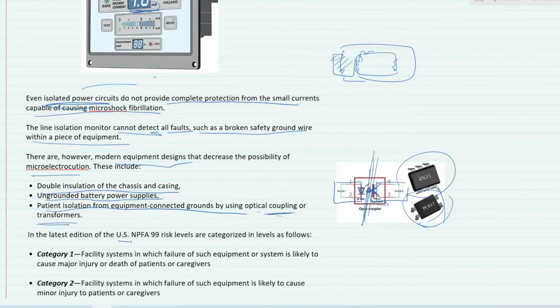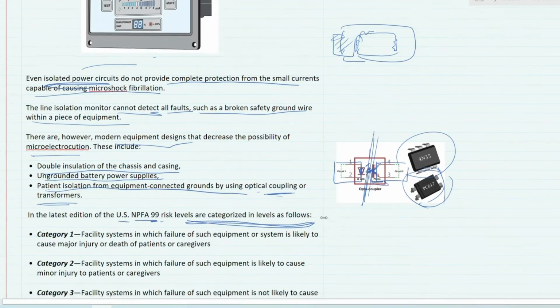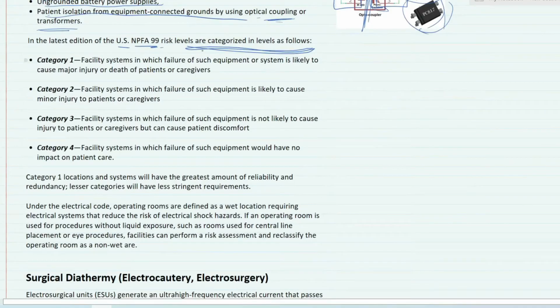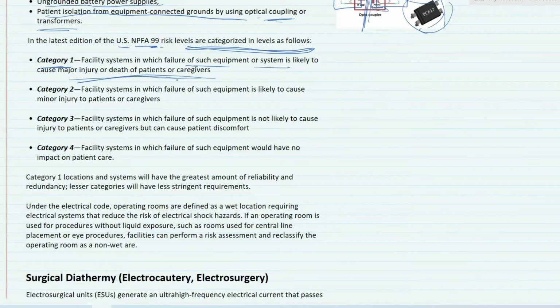In the latest edition of the US NFPA 99, risk levels are characterized as follows. There are categories in which the areas of the facilities are categorized. Category 1 facility systems are those in which failure of equipment or systems is likely to cause major injury or death of patients or caregivers, right? Category 2 would be facility systems in which failure of such equipment is likely to cause minor injury to patients or caregivers. Category 3 is where such equipment is not likely to cause injury to patients or caregivers but can cause patient discomfort. And category 4 is a facility system in which failure of such equipment would not have any impact on patient care.